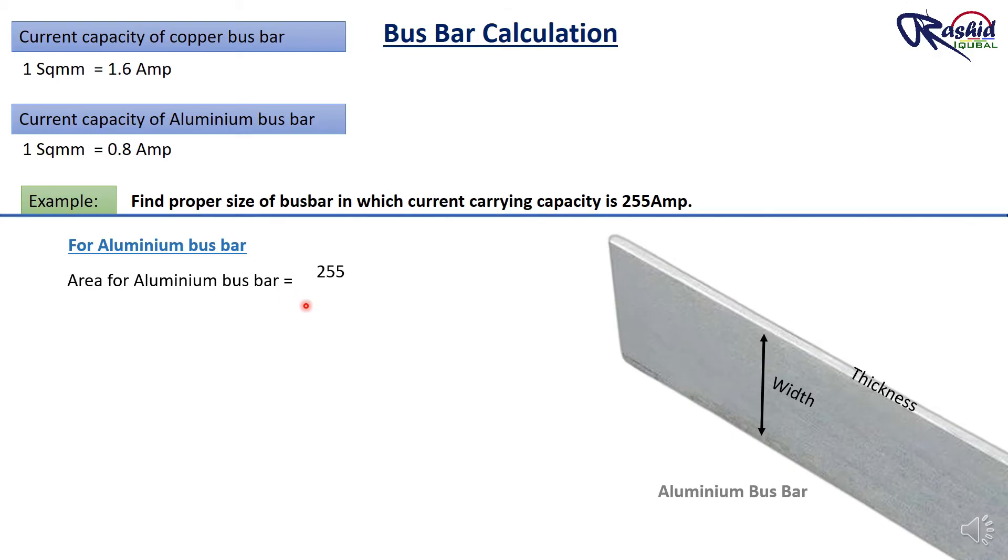The area of aluminium busbar is calculated as follows. Area equal to 255 divided by 0.8. After solving this equation, we get 318.75 square mm. That means we required 318.75 square mm aluminium, which can carry 255 ampere current.